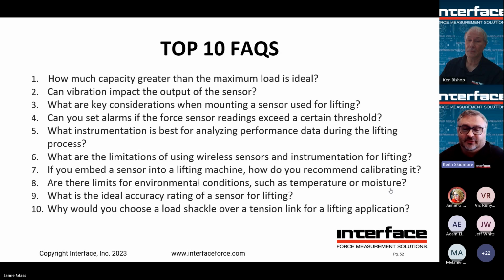What are the key considerations when mounting a sensor used for lifting? Well, one is definitely the attachment points to the device being lifted, and also the sensor and any things in line with the sensor, like clevises and rod-end bearings. Everything has to be rated for not only the load being lifted, but any safety factors that are required. Also, load cells and sensors have a load axis. It's important that fixturing and things allow the load to be aligned with the load axis.